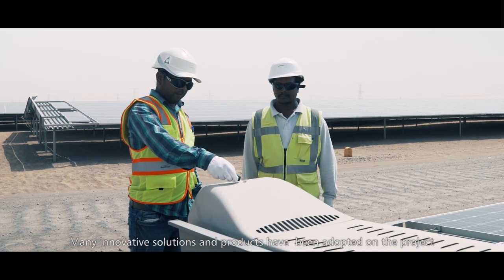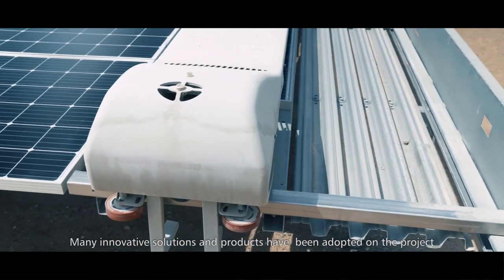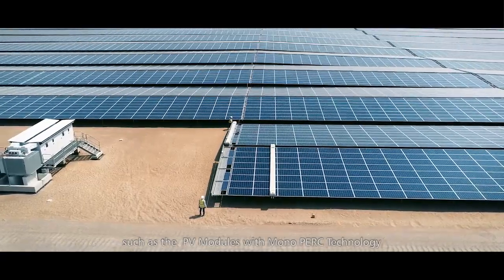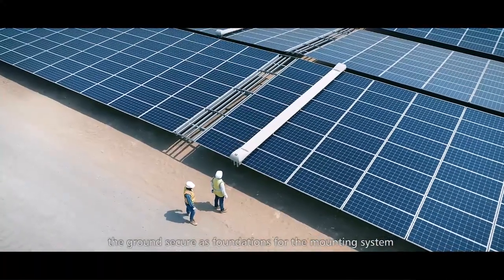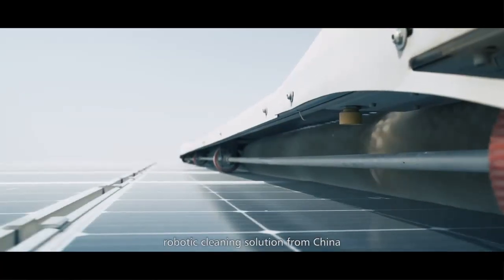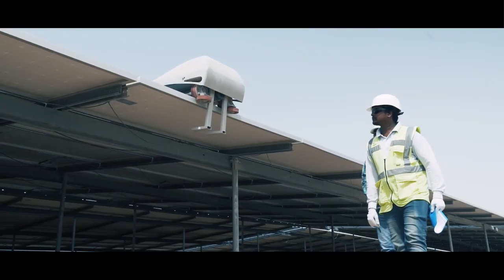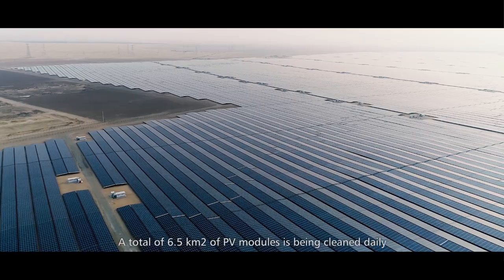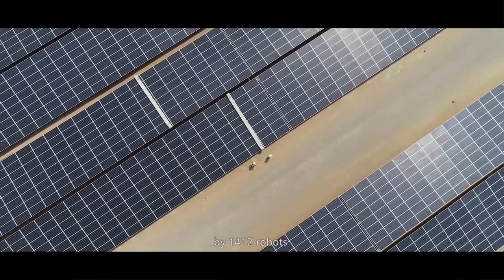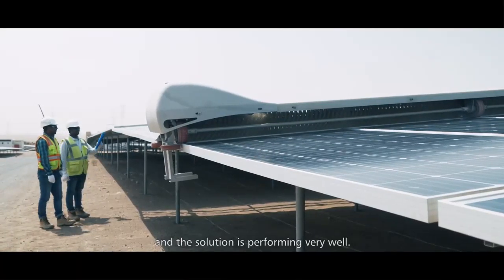Many innovative solutions and products have been adopted on the project, such as PV modules with Mono PERC technology, ground screws as a foundation for the mounting system, and a very efficient and cost-effective robotic cleaning solution from China. A total of 6.5 square kilometers is being cleaned daily by 1,400 robots, and the solution is performing very well.